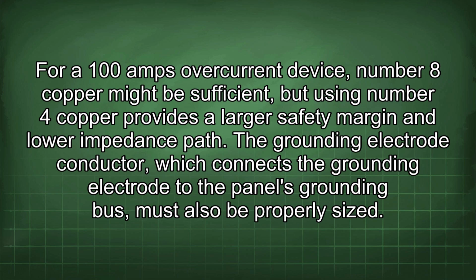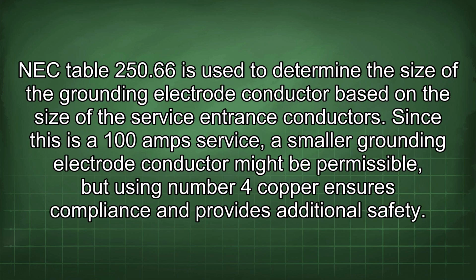The grounding electrode conductor, which connects the grounding electrode to the panel's grounding bus, must also be properly sized. NEC Table 250.66 is used to determine the size of the grounding electrode conductor based on the size of the service entrance conductors. Since this is a 100 amp service, a smaller grounding electrode conductor might be permissible, but using number 4 copper ensures compliance and provides additional safety.